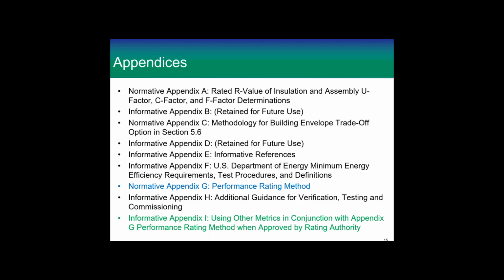Normative Appendix C is the methodology for building envelopes trade-off. So if you're going to do the trade-off methodology for the envelope, there is a method, and it's a modeling method. You'll have to run a model, but it's under kind of strict requirements so that you will have to model some HVAC equipment to see that you're saving the savings based on what the envelope is, but that's a requirement for trade-off.